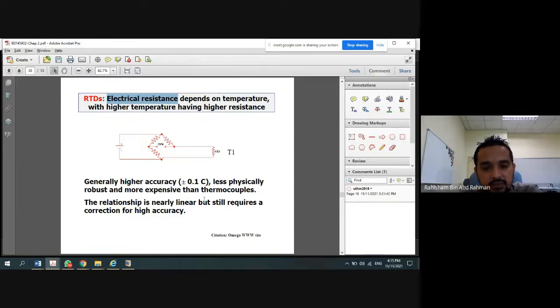And this has very high accuracy, 0.1 degrees Celsius. On the other hand, it is more expensive than the simple thermometer or thermocouples. By metal product, maybe this one is more expensive when using the RTD. Again, the sensitivity is 0.1, but for a thermocouple the sensitivity is maybe just 1 degree Celsius. So you pick whatever you need. That is how instrumentation engineers decide which type of sensor to use in each application.